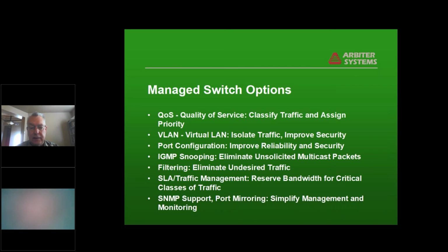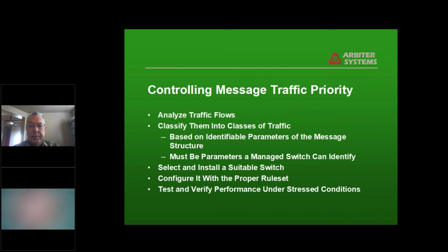You can also set up filtering to eliminate undesired traffic coming from unrelated devices. Service level agreement traffic management allows you to reserve a certain percentage of the bandwidth for certain kinds of traffic. IEC 61850 GOOSE messages, for instance, is one you might want to do that for. They also provide SNMP on switches so you can see what's going on, and port mirroring, so you can hook up a computer to a port and see what's going on with a particular device in the network. Controlling message traffic priorities allows you to give certain types of traffic higher priority than other types. This is something the managed switch can do, and you have to have the right kind of switch to do it. You have to understand what the requirements are before you buy it and make sure it's set up right. And then most importantly, you have to actually test and verify that it's working under stress conditions.